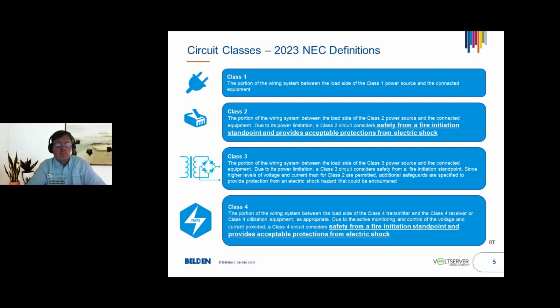And it describes the portion of the wiring system between the load side of a Class 2 power source and the connected equipment. Due to its power limitation, a Class 2 circuit considers safety from a fire initiation standpoint and provides acceptable protections from electric shock. Now, I underline that definition because I want to make a statement in regards to Class 4.